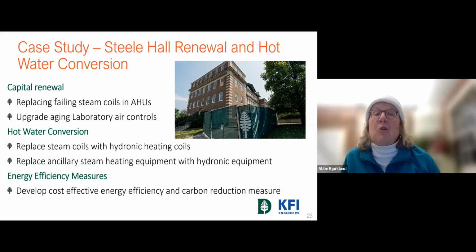We had failing steam coils in the air handlers that needed to be replaced, and we said, well, we know we want to convert our campus to hot water — let's replace those steam coils with hot water coils instead. So we looked at doing the hot water conversion for all the steam coils and steam systems throughout the building and campus, but we also looked for energy efficiency measures and carbon reduction measures as well.